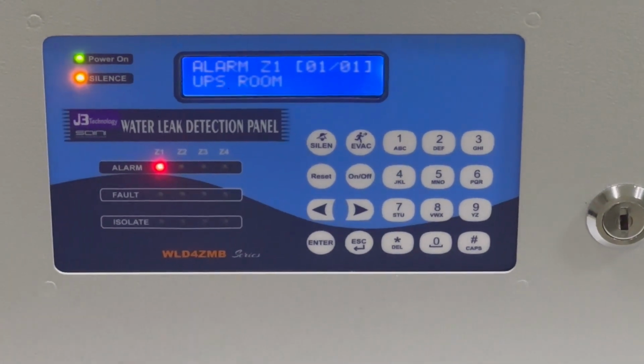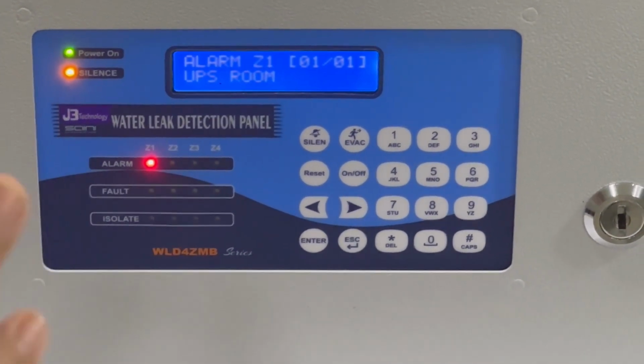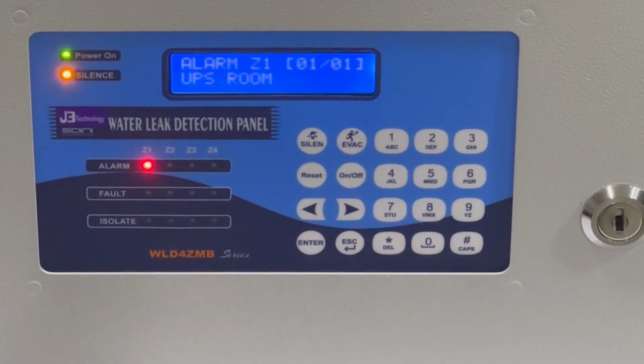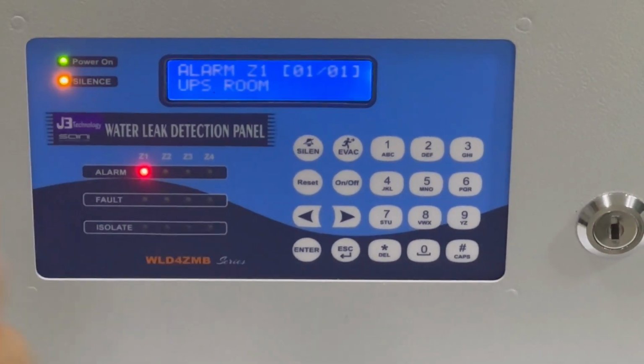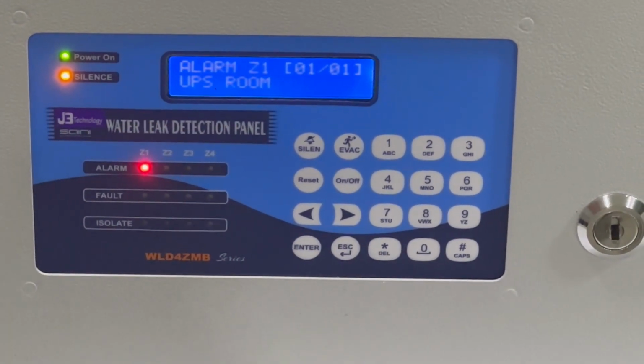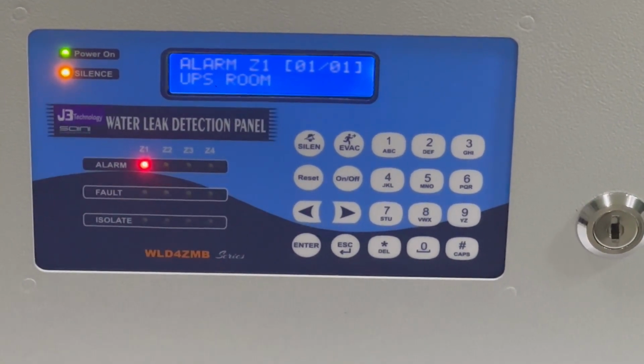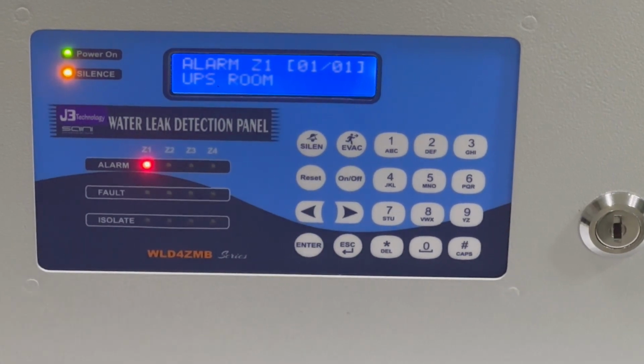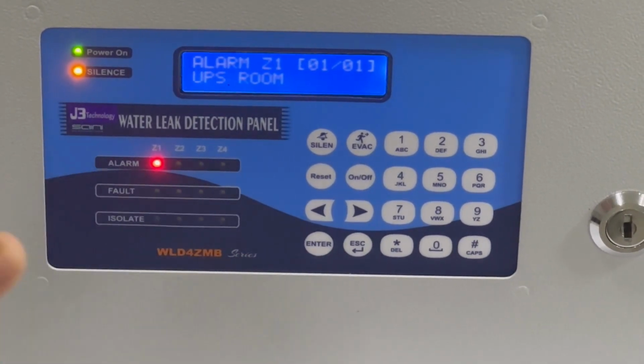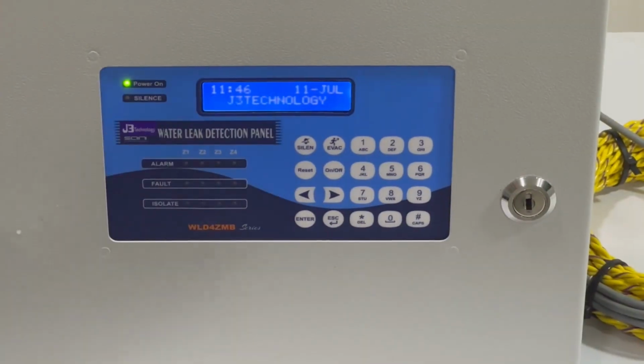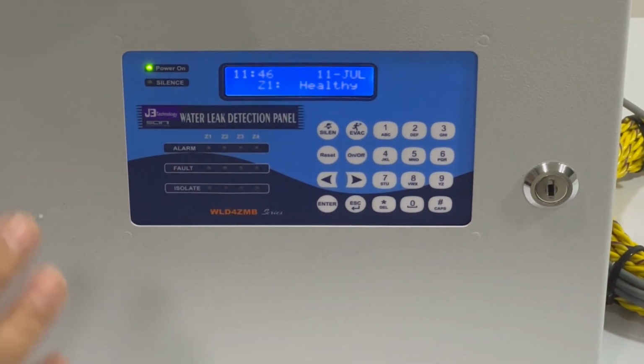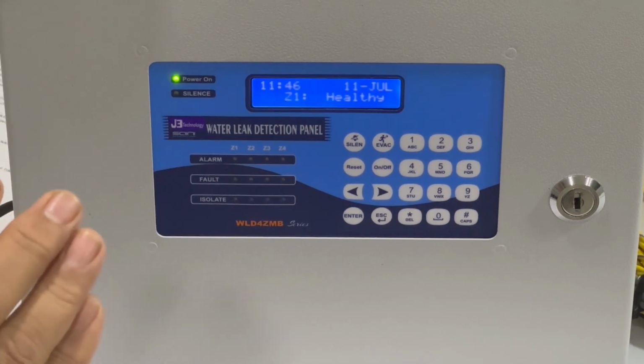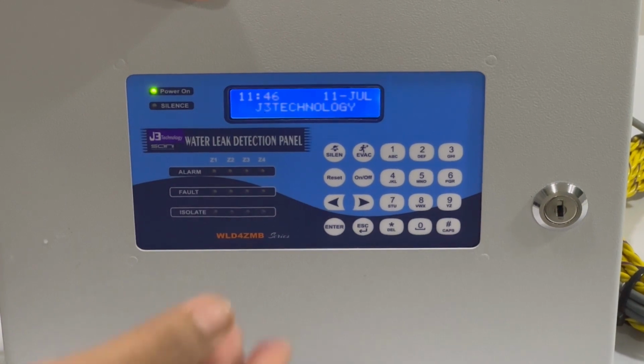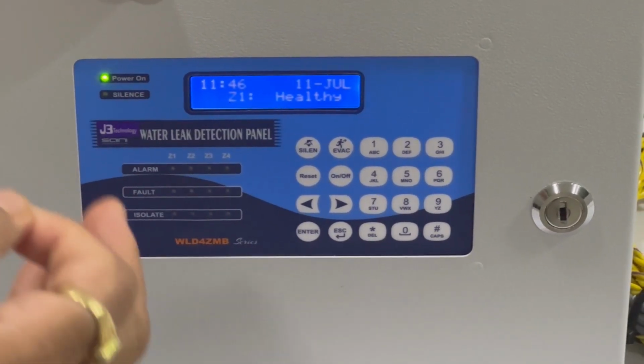Okay, this is the option in our panel only, the auto silence mode, in which you can set the auto alarm. You can define the time from how many seconds to how many hours you want the alarm. The second option is the manual option, where you have to manually come and silence the alarm. So these are features available in our panel only. The 7th option is the password. You can change the password according to your wish, or you can remove it. You can work without a password also. There is an option available in this panel. I will show you how you can change the password, or use the panel without a password.